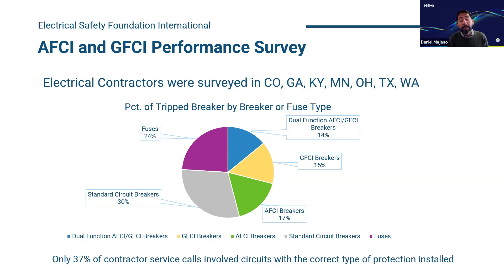And then looking at AFCIs, we did an analysis of how GFCIs have protected homeowners, consumers, and the general public since their adoption in the 70s. What we're seeing here is that between 1975 and 2020, there was a 93% drop in consumer product electrocutions. Many of these can be attributed to GFCIs and GFCI protection. And here you can see the chart. You can see GFCI protected homes in that light blue color. You can see the consumer product electrocutions with GFCI protection in the green line. You can see electrocutions in general, not just consumer products, just all electrocutions since the adoption of GFCI protection in that yellow line.